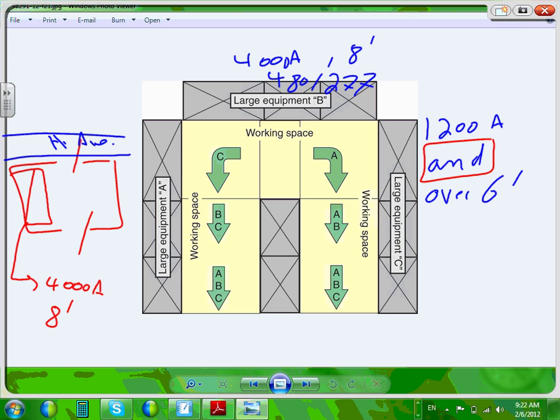If one of them in the room applies, it applies to all of them. If you're in this situation, they allow you to double the working space. So in this case, if it's 4, it's going to be 8. You can double the working space and avoid having another entrance to the room. Every electrical room has to have an entrance.